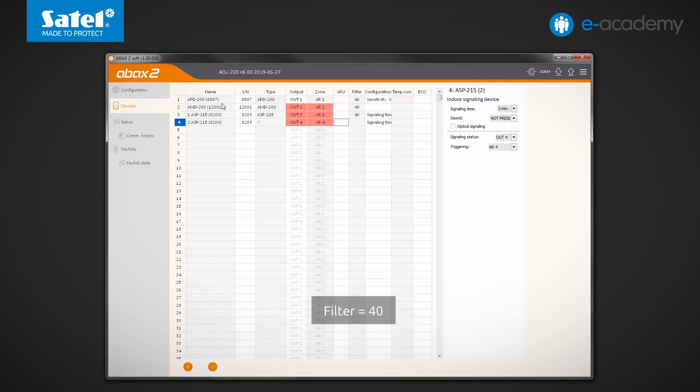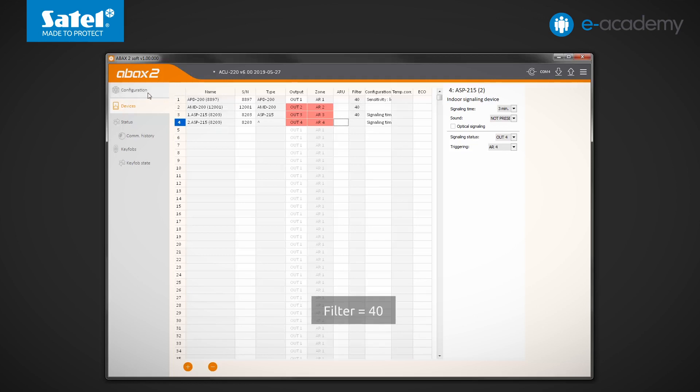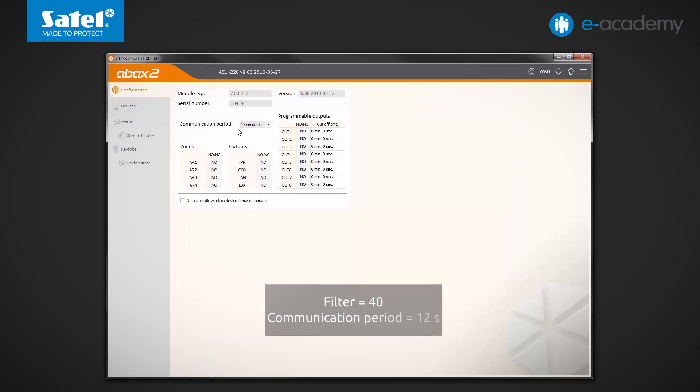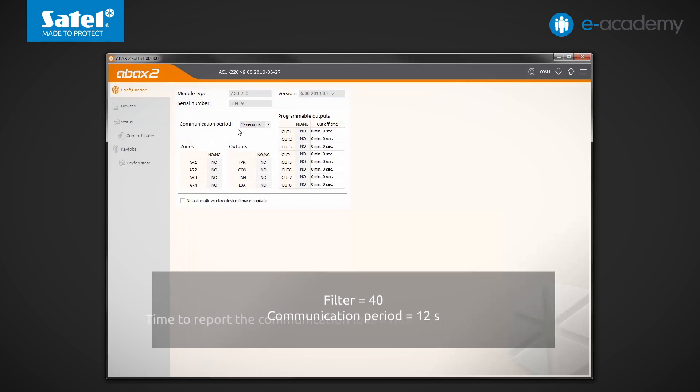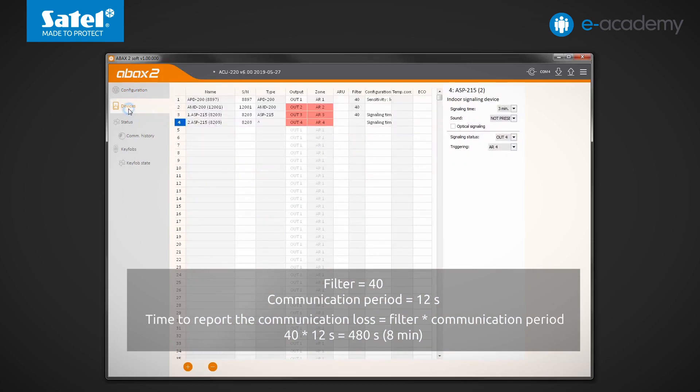Go for a moment to the configuration tab to check what communication period is currently set. Okay, it's 12 seconds. In this case, therefore, we can calculate that for a loss of communication with the selected device to be reported, a minimum time of 480 seconds must elapse. That is more than 8 minutes.